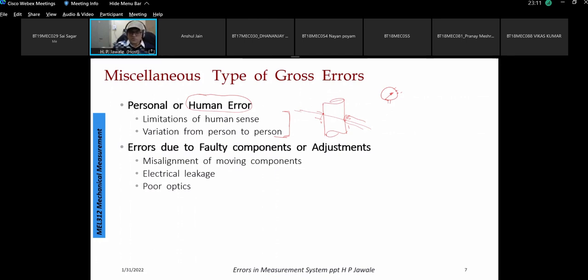Error due to faulty components or adjustment is also possible, such as misalignment of moving components, electrical leakages, or poor optics. Especially with electrical leakages, if the circuit has different ground points connected to other equipment, there can be a loss of electrons between the measurement device and the point taken as earth. You find that some charge is lost, which causes a change in the error. That's why we need to isolate properly.